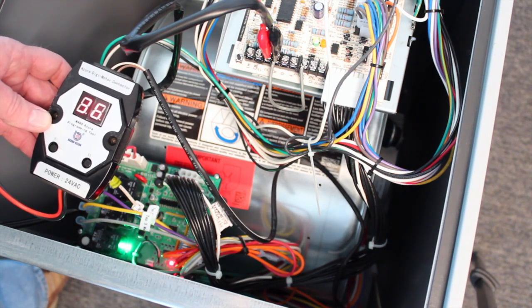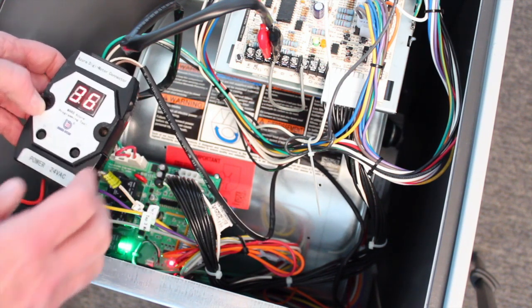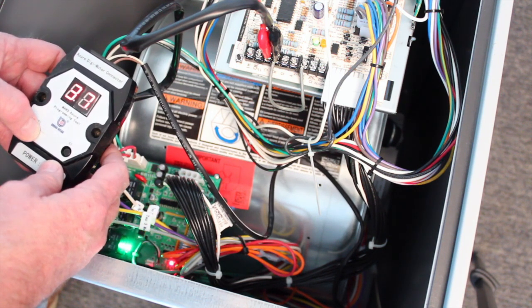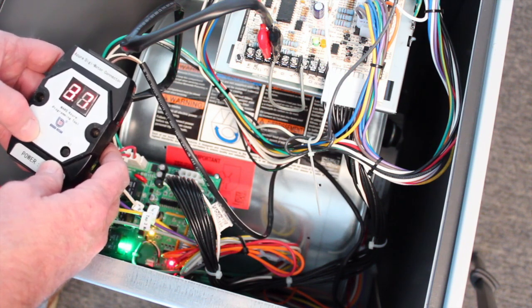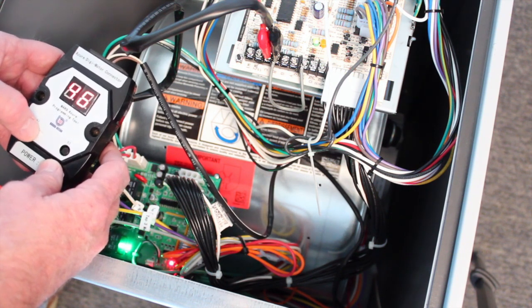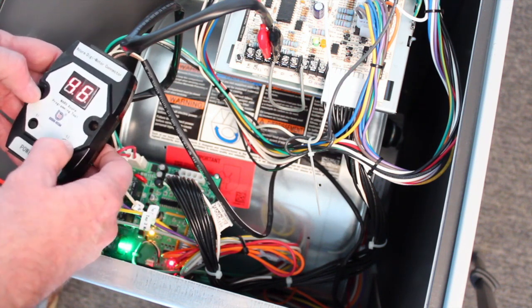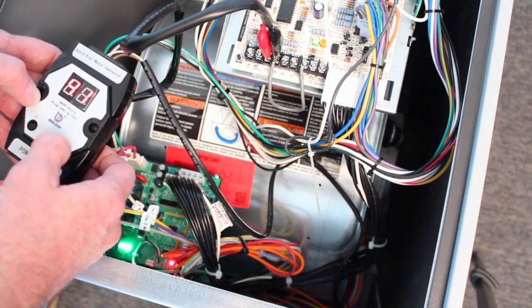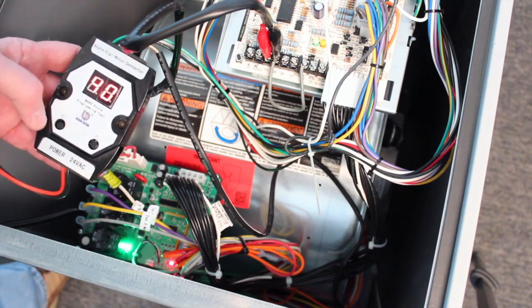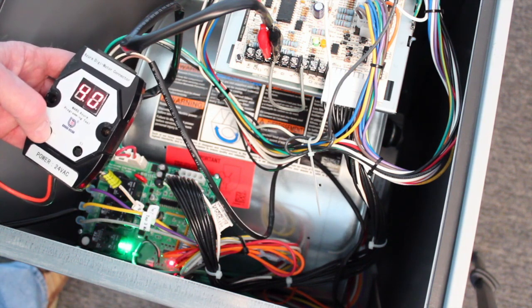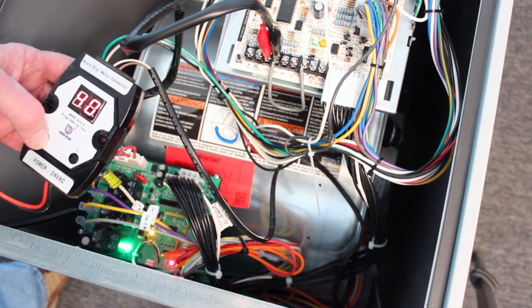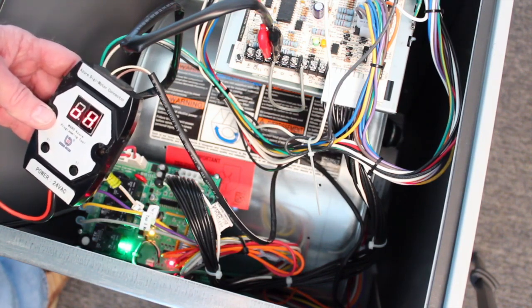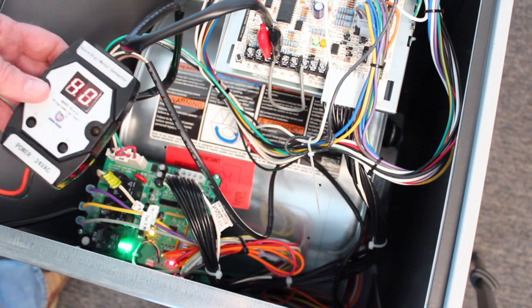If we were doing a temperature rise and we wanted to change the air flow, we can increase the air flow in 1% increments. We can do it kind of quickly here if I move like so. And let's say we want to go back down to 40, we can bring it back down. And then to lock it in, simply press the S1 button for about 3 seconds. The programmer will say OK, the motor will shut off briefly, and then come back on.